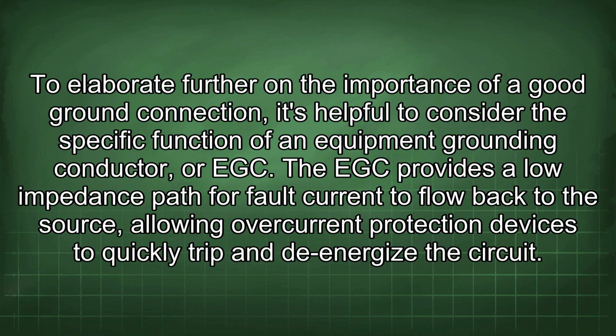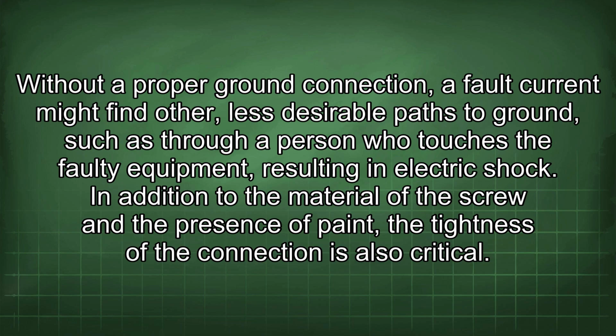To elaborate further on the importance of a good ground connection, it's helpful to consider the specific function of an equipment grounding conductor, or EGC. The EGC provides a low impedance path for fault current to flow back to the source, allowing overcurrent protection devices to quickly trip and de-energize the circuit. Without a proper ground connection, a fault current might find other, less desirable paths to ground, such as through a person who touches the faulty equipment, resulting in electric shock.